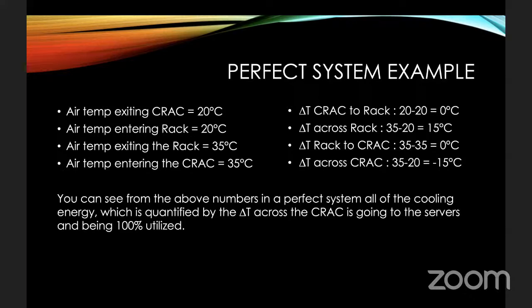The delta T across the rack is 35 to 20. So we always expect an increase of temperature across the rack. That shows that our cooling is doing something. It is entering the rack and it is carrying away 15 degrees of energy, which is energy work done by the servers. Remember, the heat inside of the servers is a direct byproduct of the amount of work they are doing. The harder the servers work, the more heat they will generate, the bigger the delta T you are going to see, up to a point whereby you are providing insufficient cooling for the capacity of that rack.